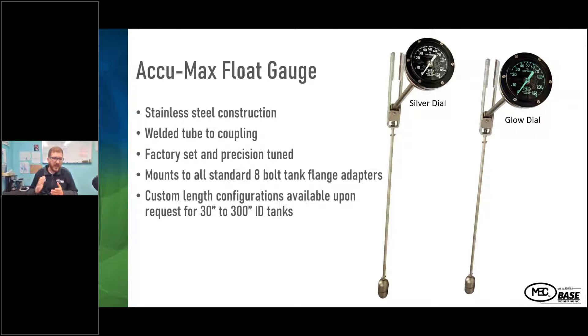All the components behind the analog dial and the digital dial are the same. There's stainless steel construction, welded tube to coupling, they're all factory set and precision tuned, and they're all made to each tank. So if there's a 72-inch tank or a 74-inch tank, we work to make sure the gauge is going to be accurate for that size tank. We're able to change the sizing to accommodate cross members or beams inside the tank. We make many more configurations than we have listed in the catalog, and we look to make a gauge that fits that particular tank.